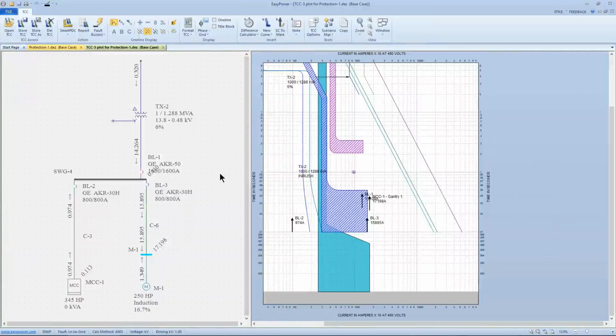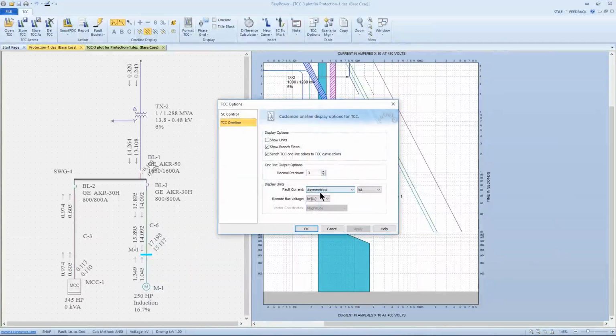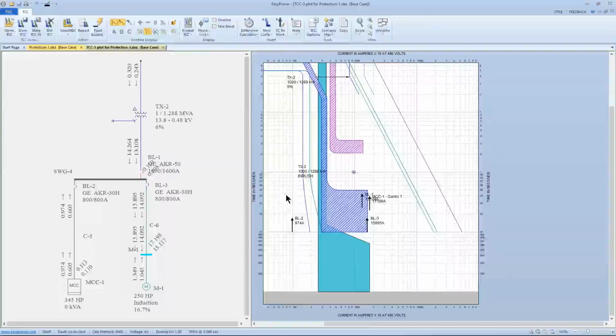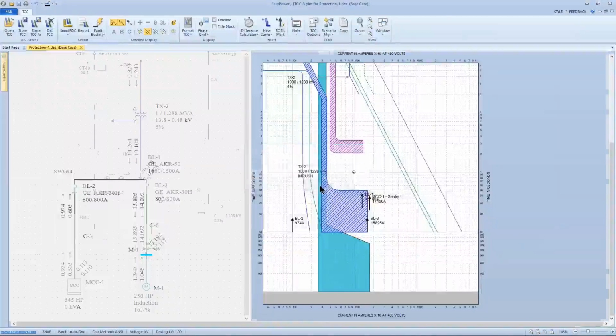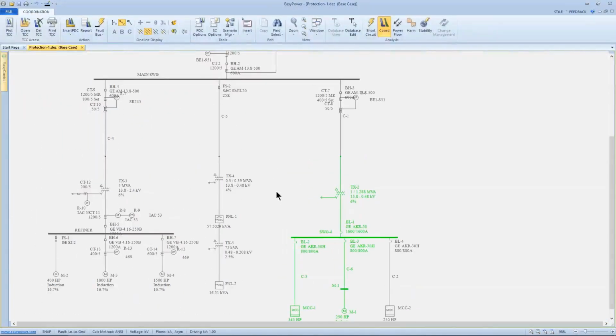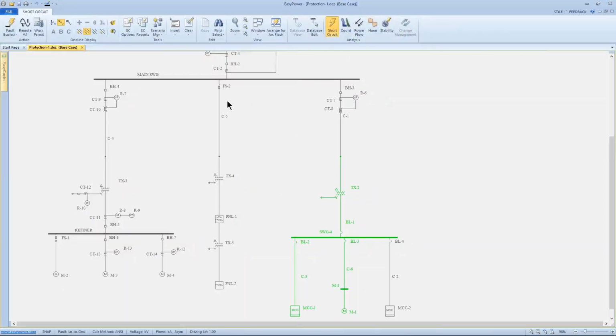Okay, so the things we've emphasized is where the different currents can be displayed. It will change at the point of calculation based upon the DC contribution for that fault. For instance, half cycle versus 5 cycle, you should see less asymmetric current. It can be displayed usually on the TCC one line and on the TCC itself based upon the options I've selected. And likewise in short circuit current, we have the ability to change the way the calculations are being made for X over R, all of which affect our short circuit analysis and ratings or comparison ratings on the breakers themselves.